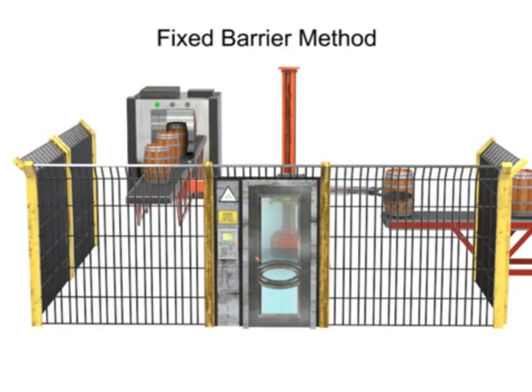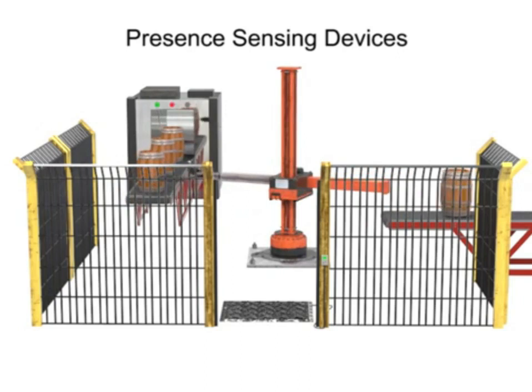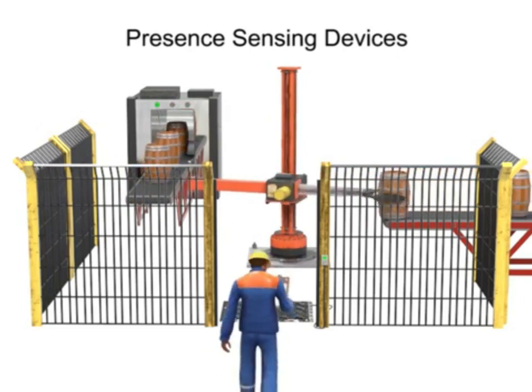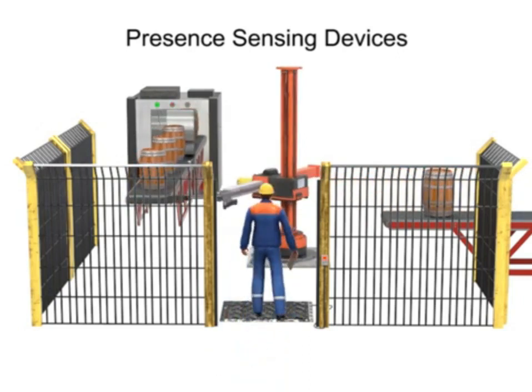Another method of protecting the robot's work envelope employs the use of presence-sensing devices. These devices detect the entry of a person into a hazardous area and slow or stop the robot. Pressure mats are typically installed just outside the robot's work envelope. When a person steps on the mat, a signal is sent to the robot to stop or slow work.